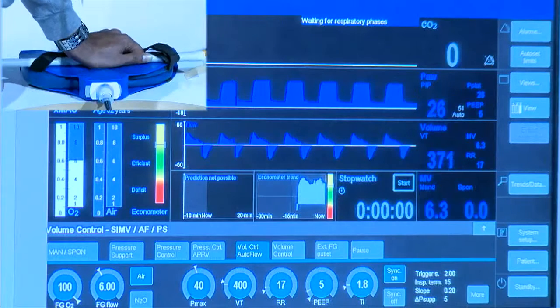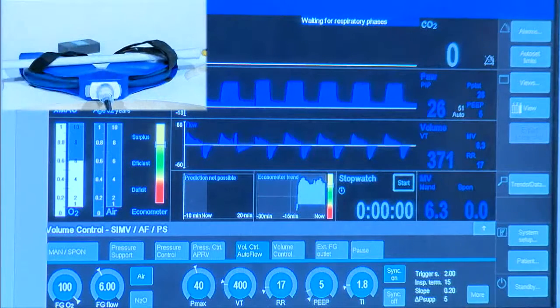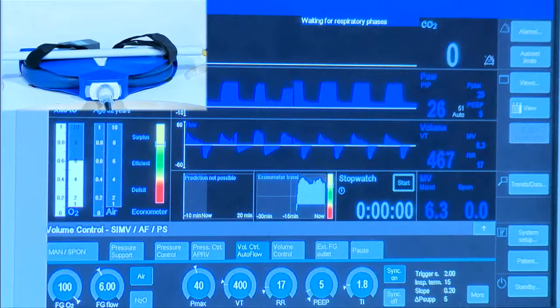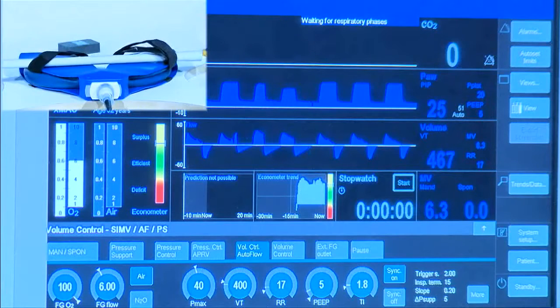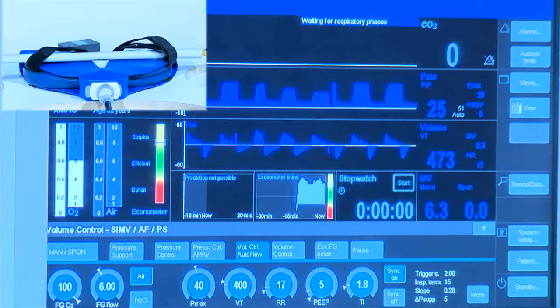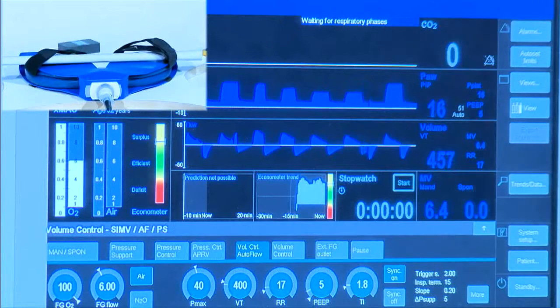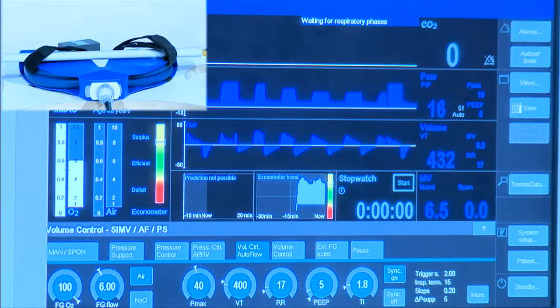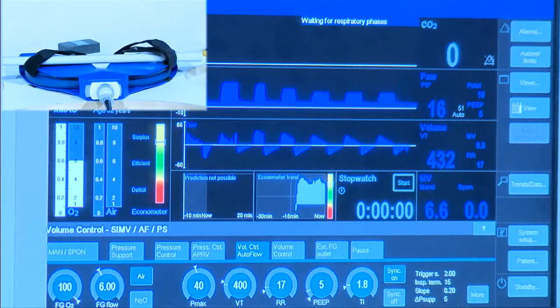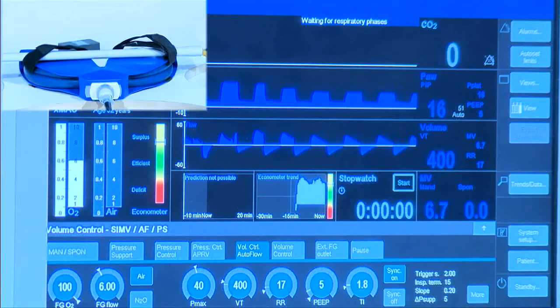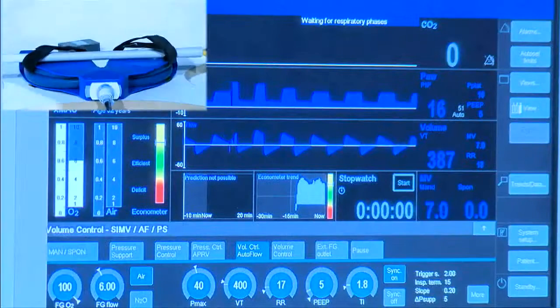Thank you very much. Okay, as soon as we release that air, up we come, and now at the end of the case, all of a sudden, you can see those flow curves are different. If you look at that inspiratory flow curve, it's a bit truncated now, and the time constants have changed. So looking at the flow curves is very important. If I was to make an obstruction here, let's put it into, I'll get the rate down a bit, and I'll show you what an obstructed airway looks like.